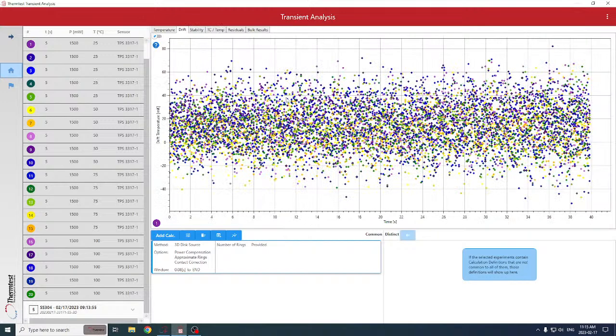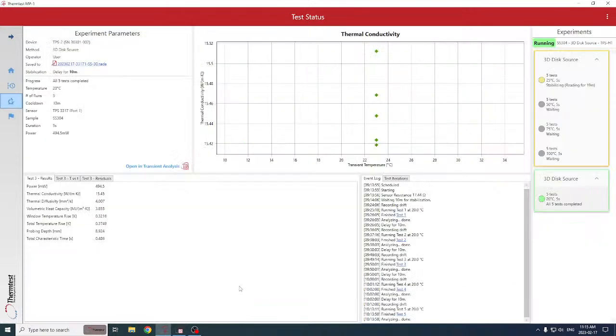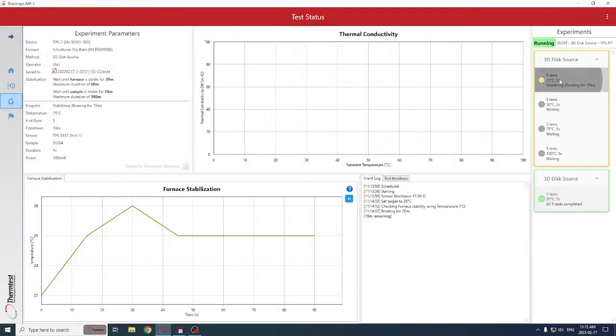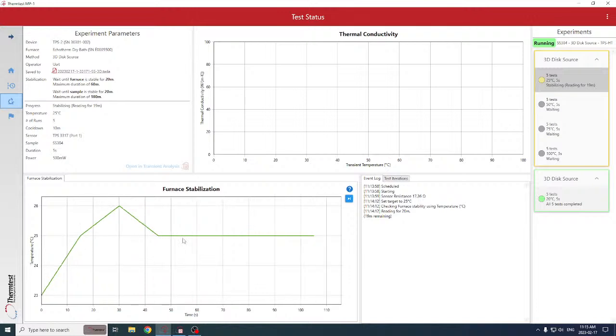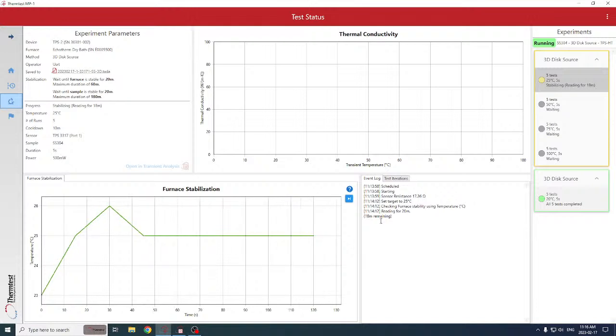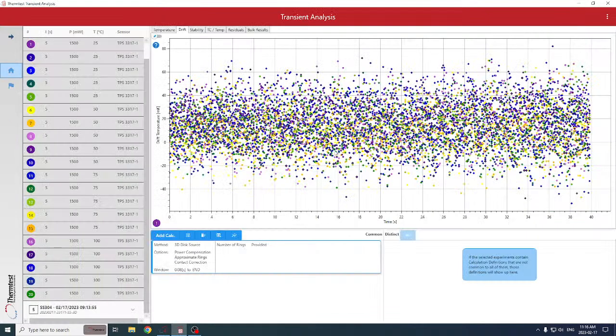Drift. So in advance of every measurement, it automatically detects a drift. So when you're running temperature measurements, there's automatically a two-stage process that if we go back to the data acquisition side and look at where the first experiment is at, we have not reached stability for 25. So the room's sitting at 23. This will have to heat up 2 degrees and become stable. We will monitor the stability of temperature at the furnace level or the controller level, and then we monitor the stability of the temperature at the sensor level. So it's a two-stage confirmation of isothermal conditions process. That ensures that no matter what the temperature is, it's isothermal. That's really important. This is confirmation of that.